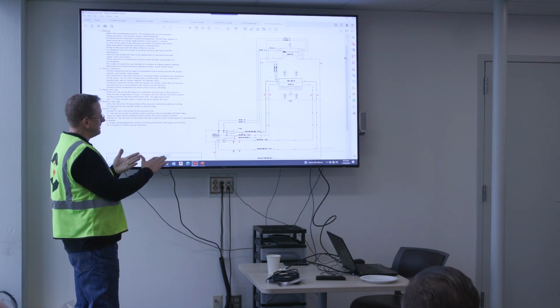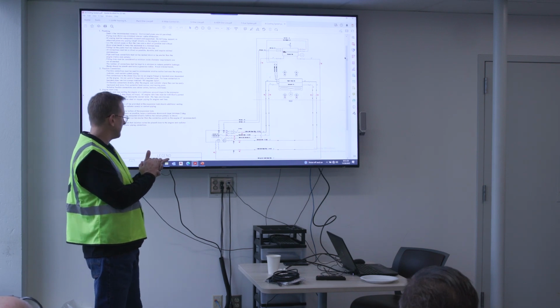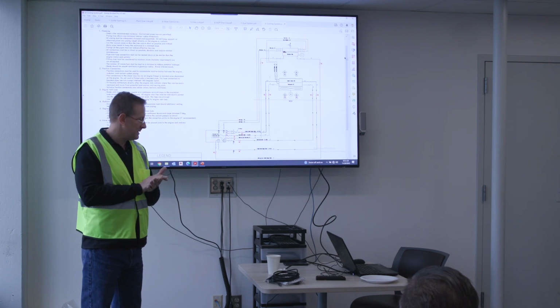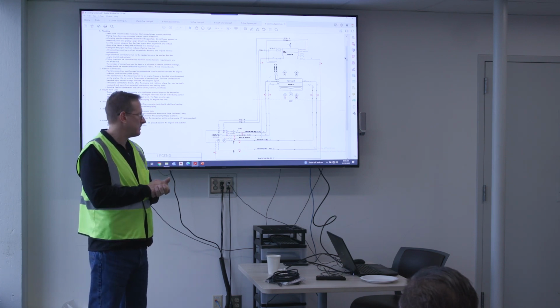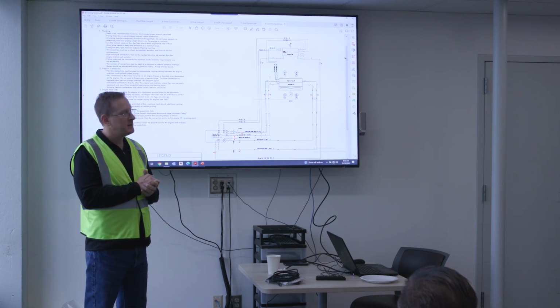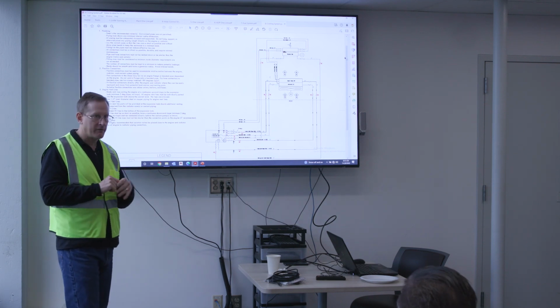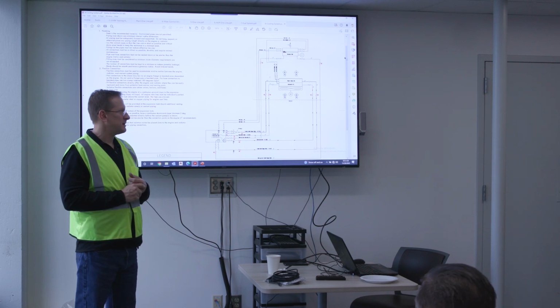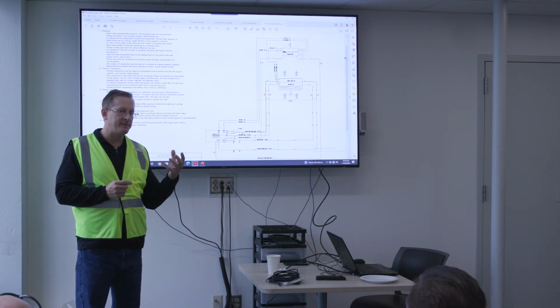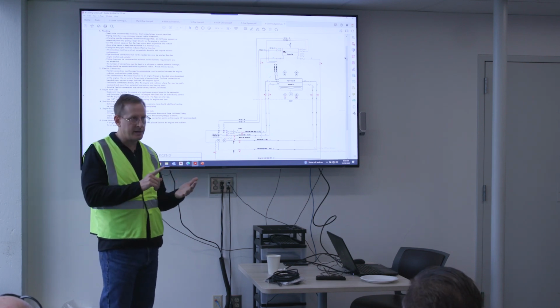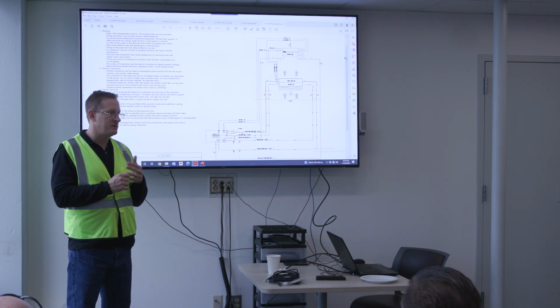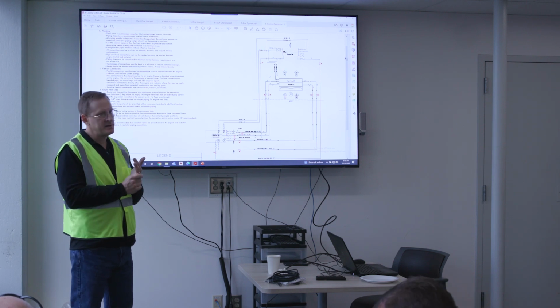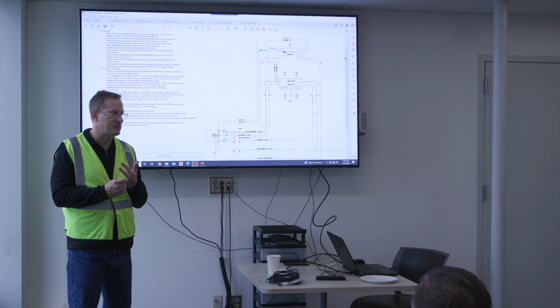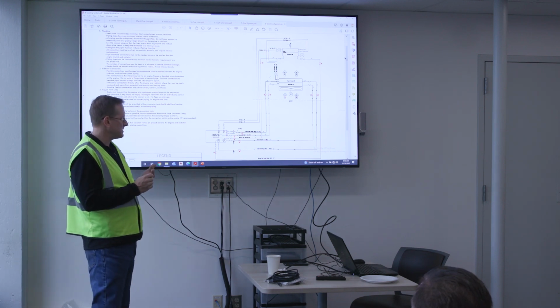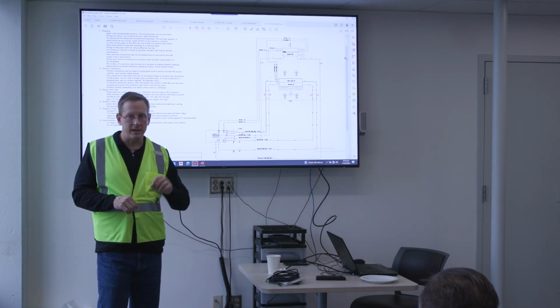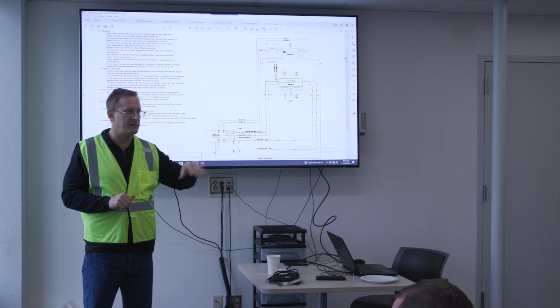Other than the fuel system and the cooling system, the only other auxiliaries for the system are the exhaust system, which is just a very basic silencer with exhaust piping all the way up through the roof. And then, of course, I mentioned we have some ventilation fans that we provide power to. Those fans basically have their own controls. What we do provide the fan is two signals. We provide the fans with either a unit running signal or a diesel running signal, and then the fans will use those two signals to regulate their operation, their speeds. They may also be thermostat driven as well. But all we do is basically tell the fans if the unit's running or if the diesel's running, and then the fans are programmed through their own controls to operate however they need to maintain airflow over the engine.